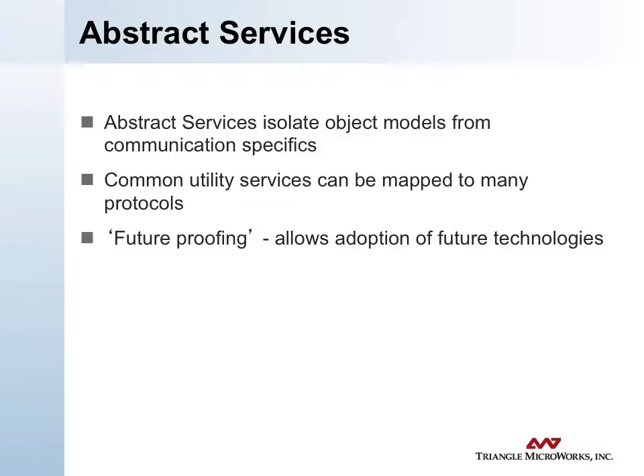These abstract service definitions are intended to isolate the object models and the applications from the communication specifics. Common utility services like get value, set value, and select before operate are common across a broad range of utility applications and can be mapped to almost any kind of protocol. This future-proofing allows us to adopt new technologies without disturbing the whole system, and it builds in a migration strategy directly into the way that 61850 has been defined.